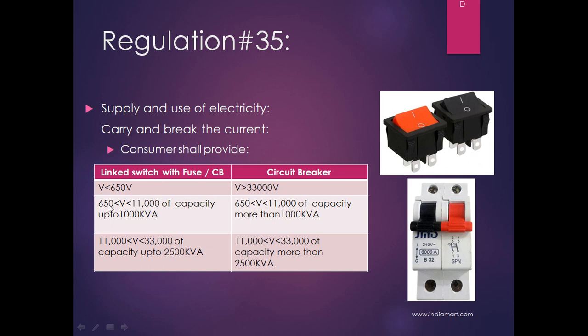For voltage level from 650 volt up to 11 kV, and if the load capacity is up to 1000 kVA, then linked switch with fuse or circuit breaker can be provided. But if the capacity exceeds 1000 kVA, then only circuit breaker has to be provided. If the voltage level is more than 11 kV but not more than 33 kV and capacity is up to 2500 kVA, then linked switch with fuse or circuit breaker can be provided. But if the capacity is more than 2500 kVA, only circuit breaker shall be provided by the consumer.